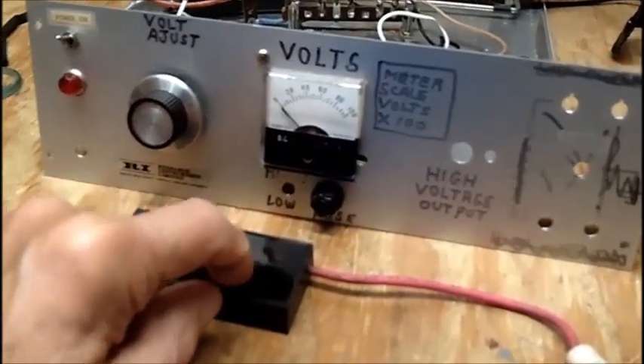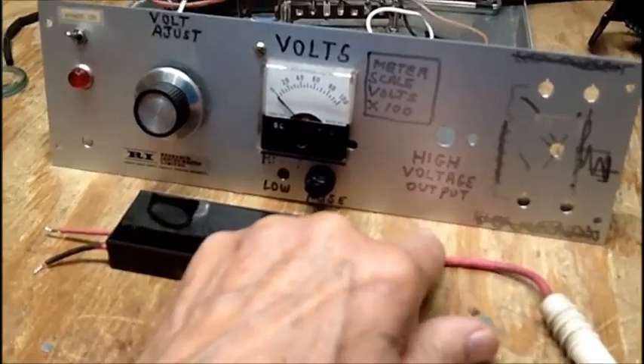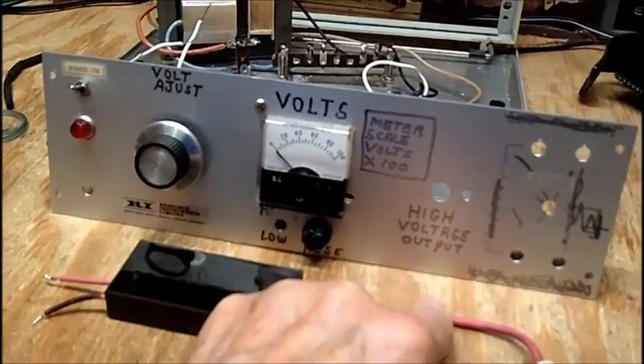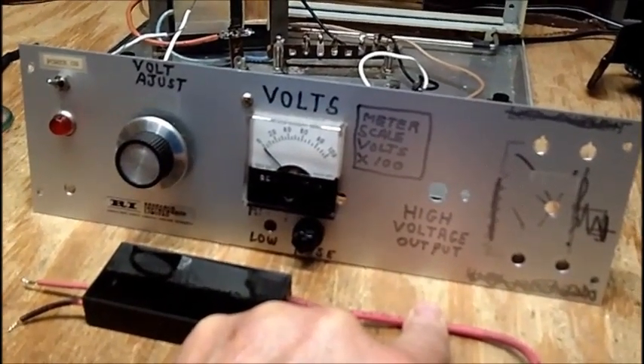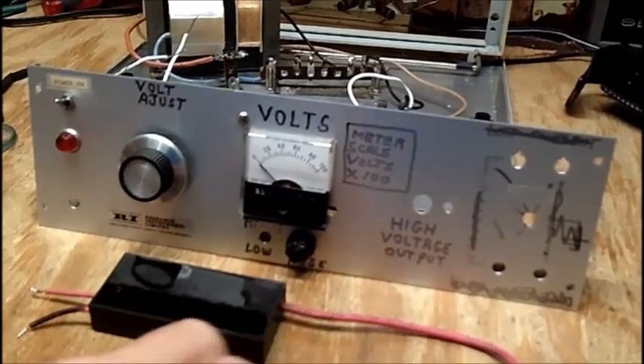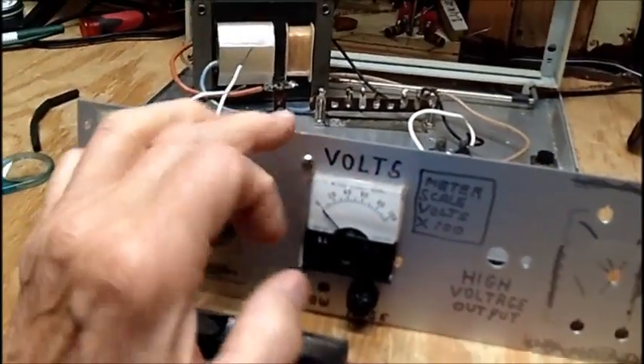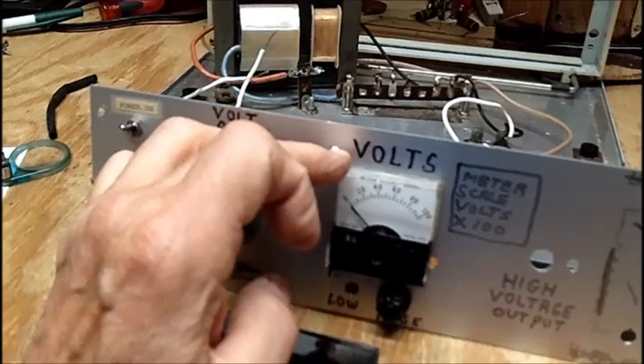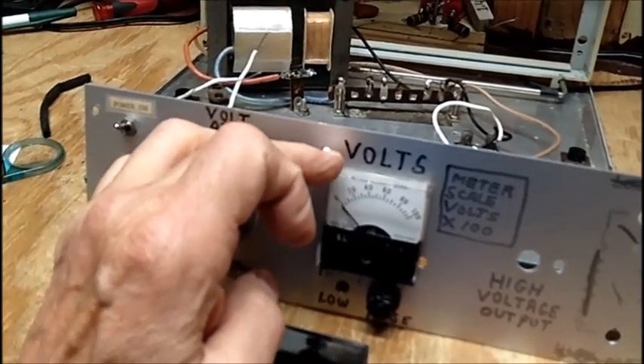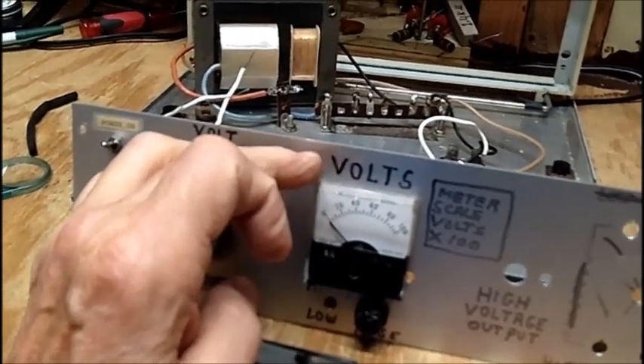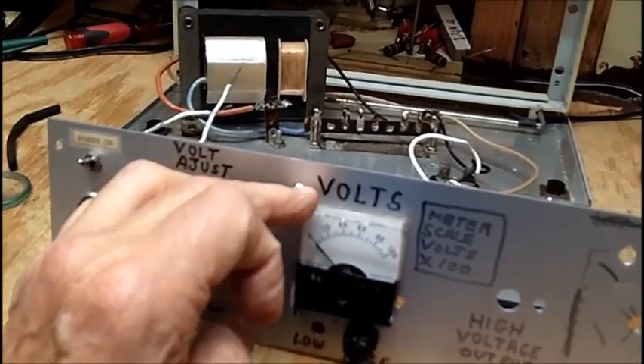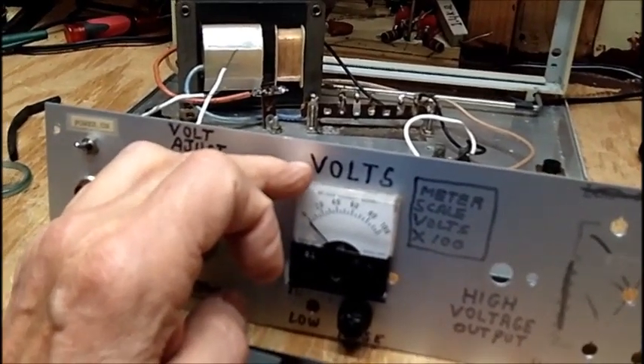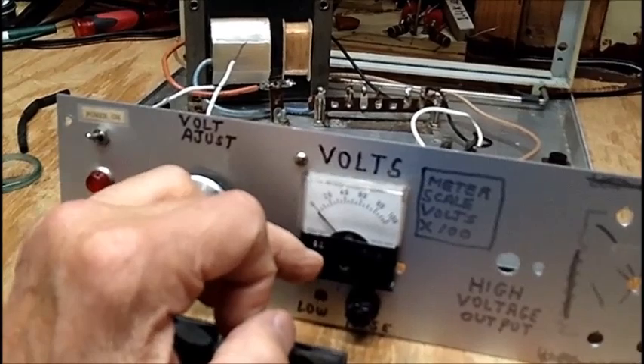So whatever comes out of here is going to be sucked down a little bit with 100 megohms of resistance to ground through this 100 microamp meter. It's going to be full scale. The max draw would be 100 microamps because that's what this meter is.